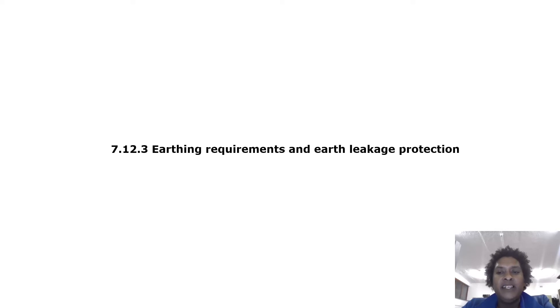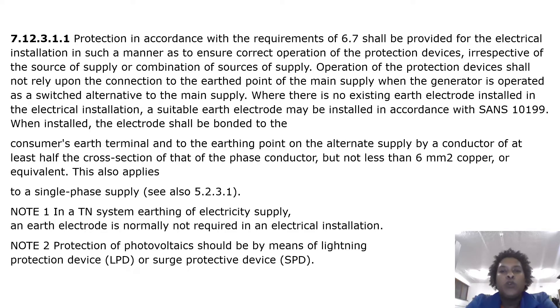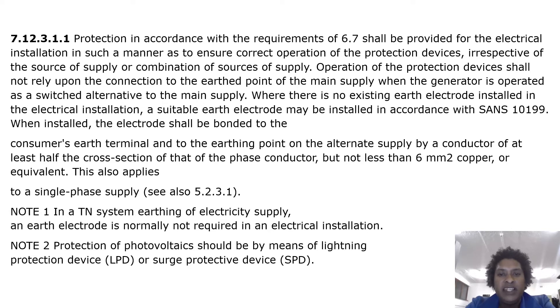Earthing requirements and earth leakage protection: protection in accordance with the requirements of 6.7 shall be provided for the electrical installation in such a manner as to ensure correct operation of the protection devices irrespective of the source of supply. Operation of the protection devices shall not rely upon the connection to the earth point of the main supply where the generator is operated as a switched alternative. Where there is no existing earth electrode, a suitable earth electrode may be installed in accordance with SANS 10199.